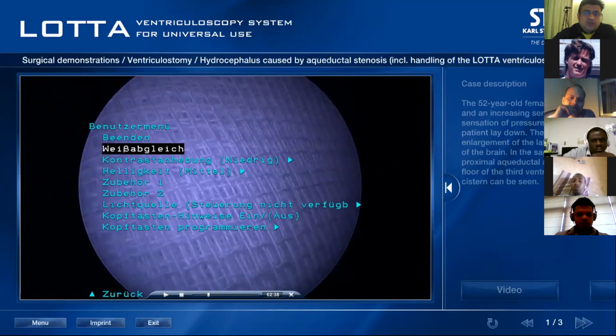So once you do the white balance, if you are using the same xenon light source, and not changing the light source between a xenon to metal halide or a halogen, there is no need to do white balancing, and you can save a lot of anesthesia time, which is very, very important for the operating surgeon. And many times surgeons are redoing the white balance, and in a hurry, they take an angle scope and the whole surface is not covered with white, and it senses the color of the sterile drape, and you do not get a very good color.